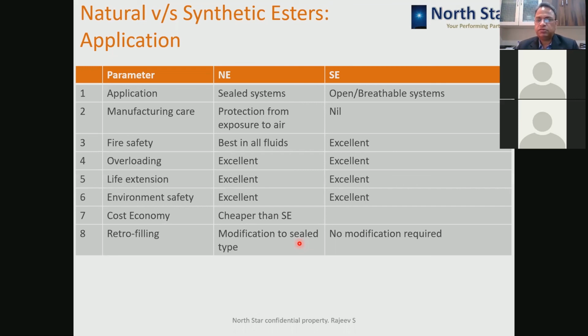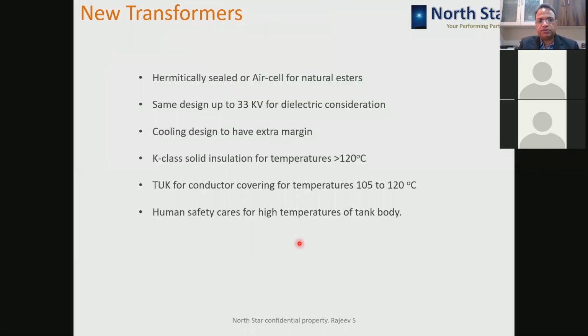Only thing with the synthetic ester, you don't have to do any modification to the breathing system. As such, you can use it. And for natural ester, as you know, you have to go for a sealed type of arrangement. So you have to modify the transformer a little bit so that you can prevent exposure of the liquid insulation to the air. So that is the application comparison of synthetic as well as natural esters. For a new transformer, for the application, you need a hermetically sealed or air cell arrangement for natural esters. You can have the same design, meaning the same clearances and the same insulation arrangement, up to 33 kV as far as the dielectric consideration is concerned.